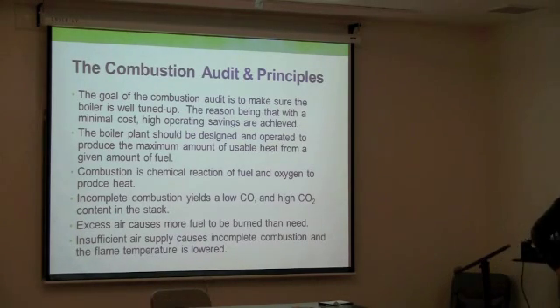When it comes to physical plants building, when you go to audit building, you see a lot of boilers. When it comes to boilers, it's very important to make sure that the burner is clean, the oil and the air, the gas that is coming and the air has a perfect ratio, right? Because there is a combustion ratio. For example, the recommended combustion ratio for this gas is 10 to 1. That means for every unit of gas, you need 10 units of air. Now, what happens if I put 8 units of air? I'm going to have incomplete combustion. So I'm not getting energy out of my gas that I'm paying for. That's number one.